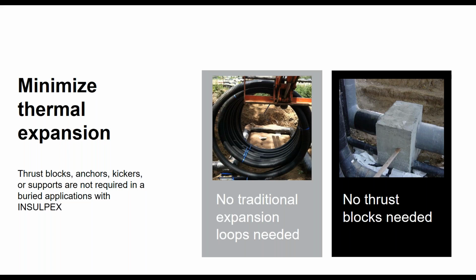This happens to be on a high temp steam system, and I'll show you the full project in a couple slides, but just as a nice visual, here's what an expansion leg looks like. We don't have to put an expansion leg into our systems. Granted, these are relatively low temp, 200 degrees and less, so the amount of thermal expansion that occurs is minimal, and what does occur happens hoop-wise, where the pipe grows into the foam ever so slightly, but the pipe itself doesn't grow lengthwise. That's the expansion loop side of it.